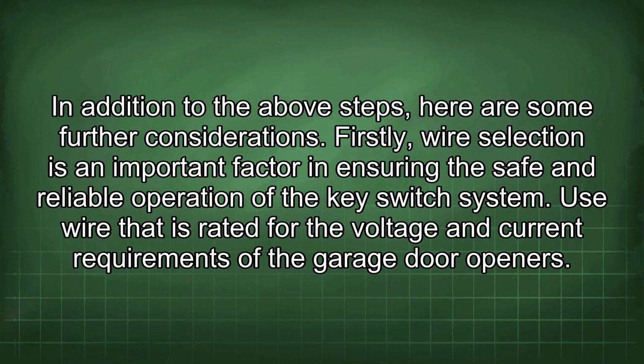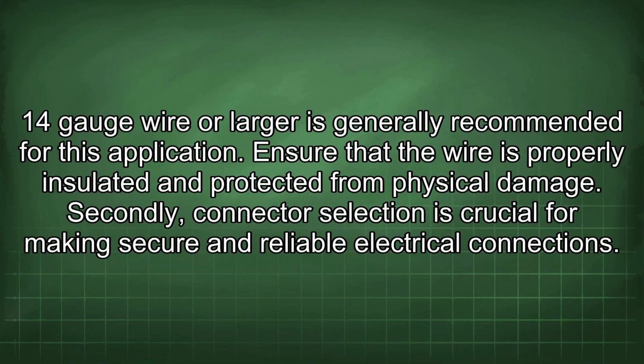Firstly, wire selection is an important factor in ensuring the safe and reliable operation of the key switch system. Use wire that is rated for the voltage and current requirements of the garage door openers. 14-gauge wire or larger is generally recommended for this application. Ensure that the wire is properly insulated and protected from physical damage.